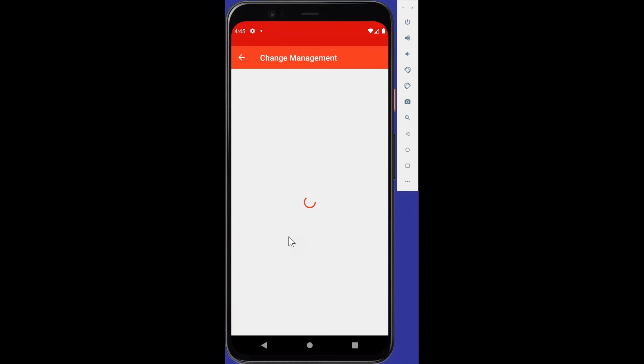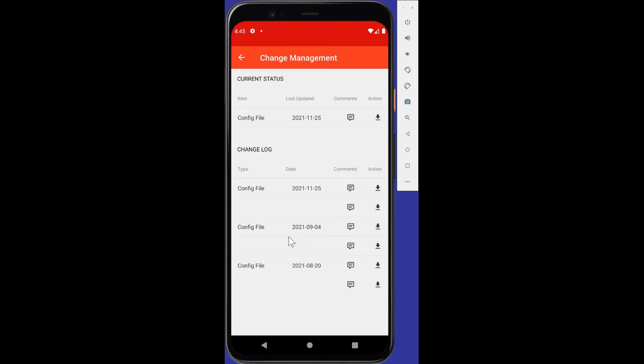Come back to this page here. Let's click change management. Let that page load for a second on the simulator. Okay, this is really important. So change management for us is where we track the configuration files or the firmware versions that are live on that pump. We know that when we go and do a startup or commissioning, or we go by a customer site and we configure the pump to operate in a certain way, literally five minutes after we leave, the end users now potentially changing those configurations for whatever reason.